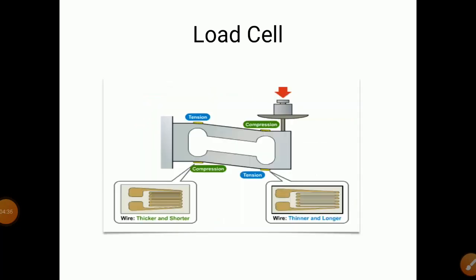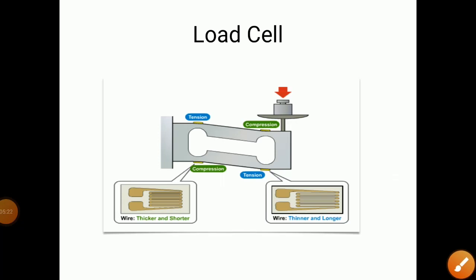Here, load is applied like a cantilever beam on one side. When you apply load, some of the strain gauges are in compression and few of them are in tension. Those in compression are thicker and shorter, while those in tension are thinner and longer. This is how the load cell works.